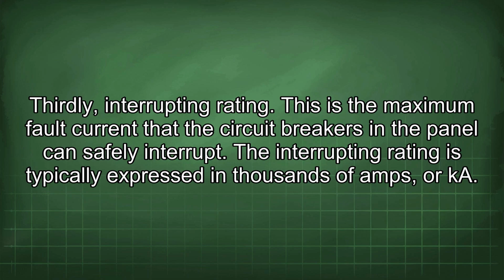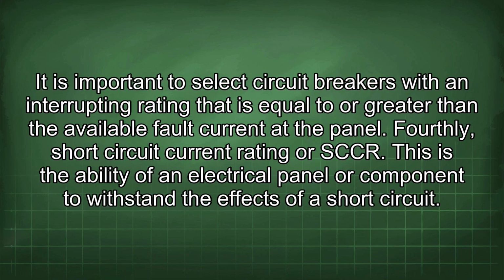Thirdly, interrupting rating. This is the maximum fault current that the circuit breakers in the panel can safely interrupt. The interrupting rating is typically expressed in thousands of amps, or kA. It is important to select circuit breakers with an interrupting rating that is equal to or greater than the available fault current at the panel.